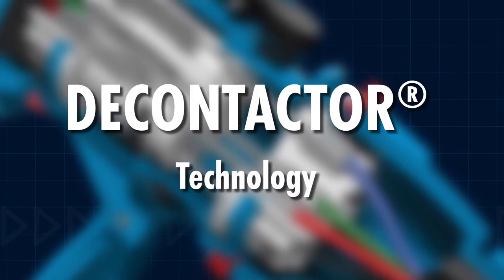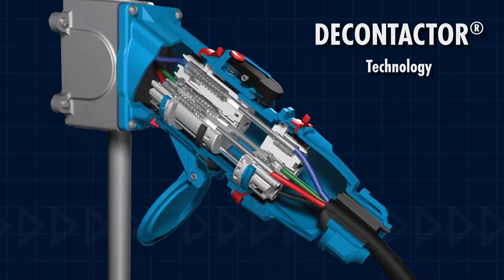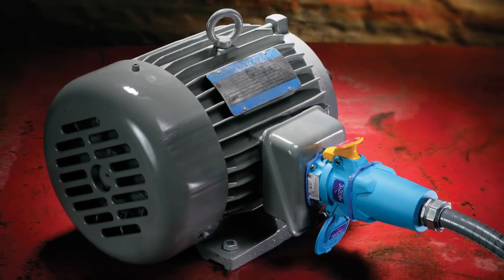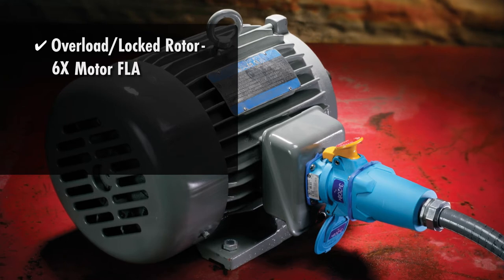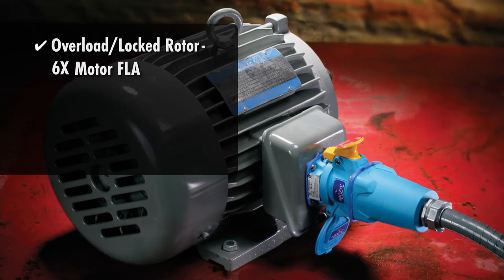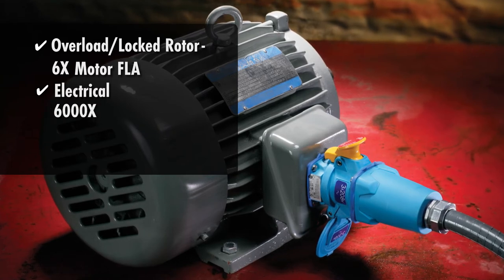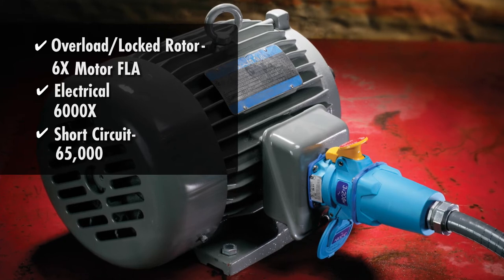Meltric exclusive Decontactor technology ensures that the plugs and receptacles are safe to connect and disconnect even in overload conditions. They have successfully passed overload locked rotor tests at six times rated full load motor current for 50 operations, electrical endurance tests at rated current and voltage for 6,000 operations, and a short circuit make and withstand test at 65,000 amps or more.